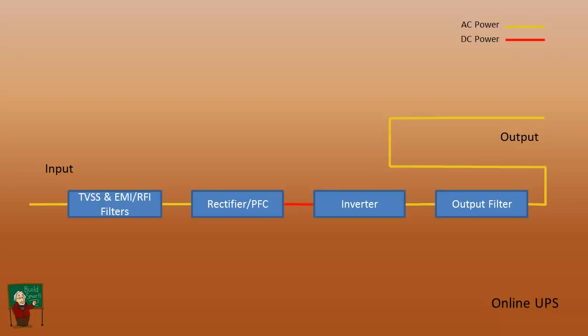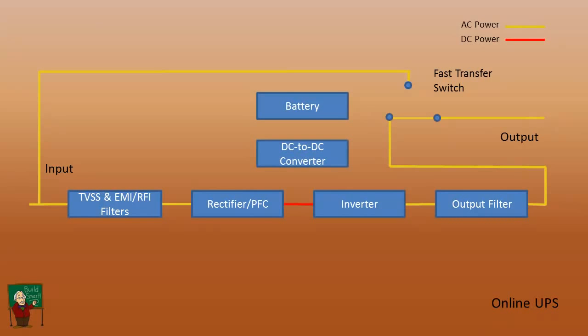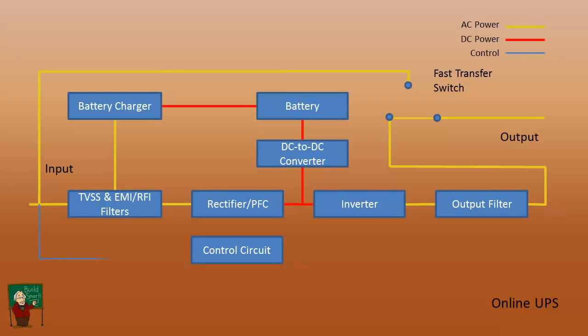And then we add some components to that. Put a transfer switch in here, although not for the same purpose as on the standby UPS. This is basically a transfer switch that's used to transfer around the whole UPS to take it out of the circuit. We'll have a battery, a DC to DC converter, which will be hooked up to the battery, and that in turn will provide power to the inverter. We'll have a battery charger, which is hooked up to the line voltage coming in, and that of course will charge the battery. Control circuit, and that'll look at the input voltage. It'll have the ability to control the DC to DC converter, turn that on when needed. It'll check the battery voltage and have the ability to turn on the battery charger to charge the battery.